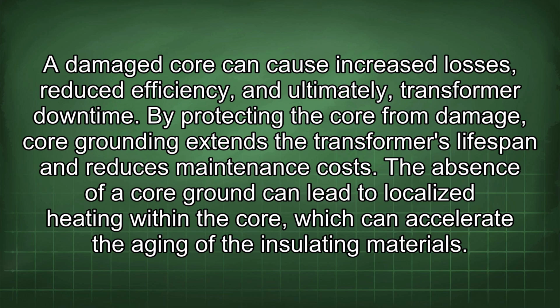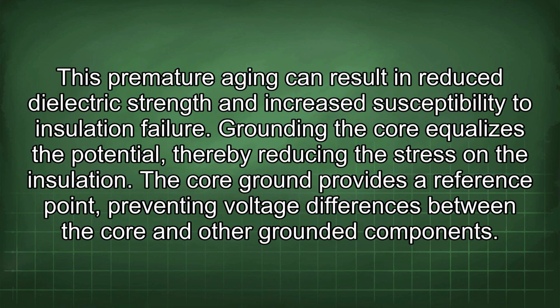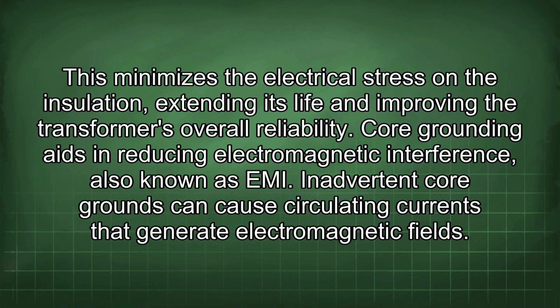The absence of a core ground can lead to localized heating within the core, which can accelerate the aging of the insulating materials. This premature aging can result in reduced dielectric strength and increased susceptibility to insulation failure. Grounding the core equalizes the potential, thereby reducing the stress on the insulation. The core ground provides a reference point, preventing voltage differences between the core and other grounded components. This minimizes the electrical stress on the insulation, extending its life and improving the transformer's overall reliability.